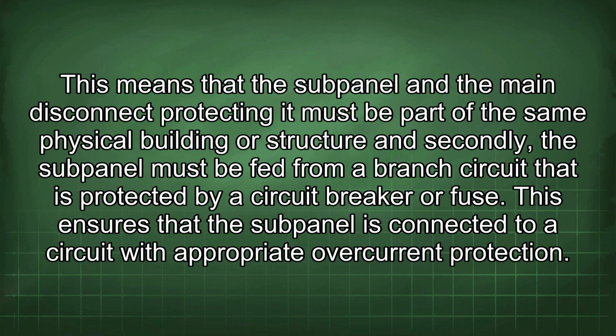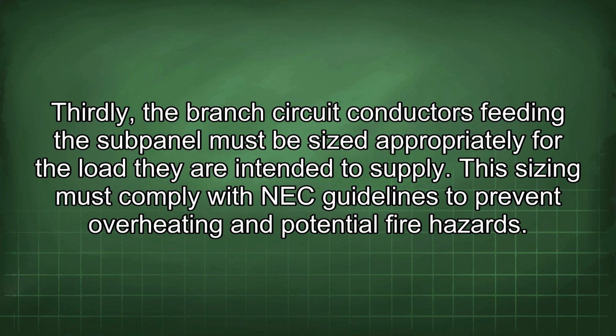Secondly, the subpanel must be fed from a branch circuit that is protected by a circuit breaker or fuse. This ensures that the subpanel is connected to a circuit with appropriate overcurrent protection. Thirdly, the branch circuit conductors feeding the subpanel must be sized appropriately for the load they are intended to supply. This sizing must comply with NEC guidelines to prevent overheating and potential fire hazards.